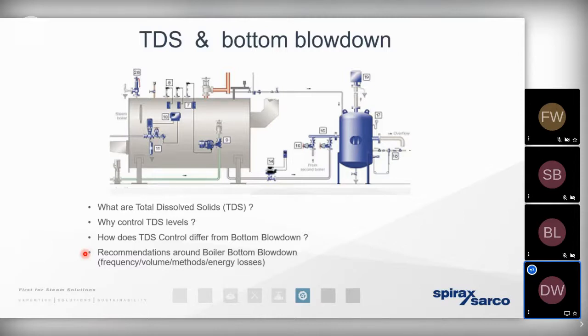And over time, if you put in more and more sugar and more sand into the tea, a number of different things are going to happen. First of all, the sand is going to start occupying quite a lot of the space within the cup. And secondly, the more sugar you put in the tea, then that tea is going to get saturated with sugar and it's going to start to get very, very frothy. So let's move that analogy across to a typical steam using boiler. The chemicals and minerals that solidify and fall to the bottom of the boiler are going to need removing. And we do that by using a bottom blowdown valve.